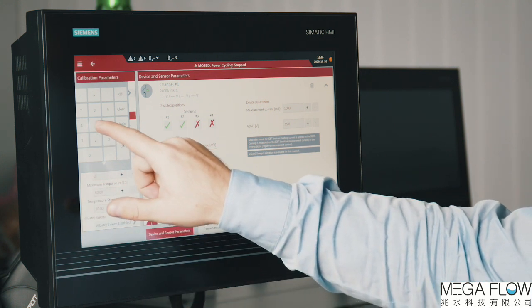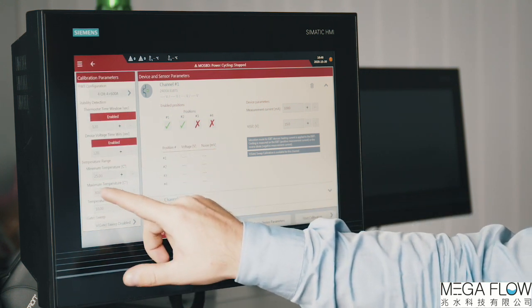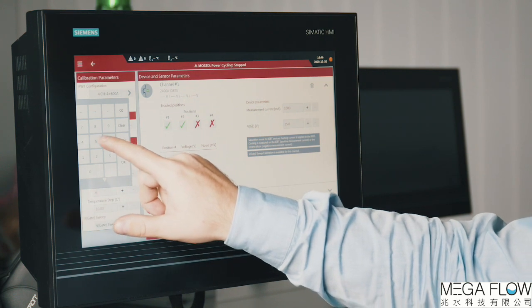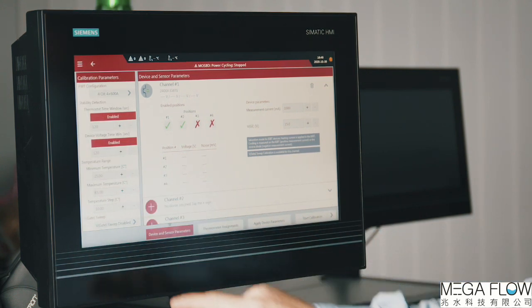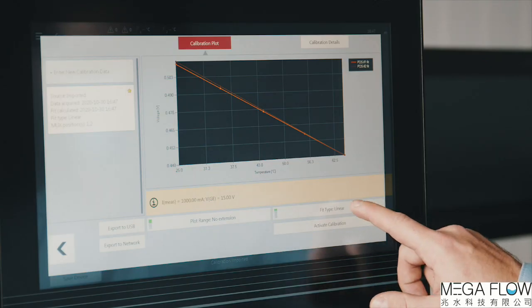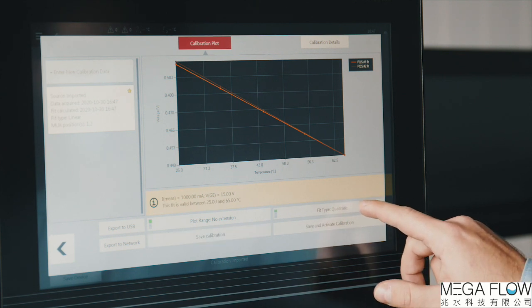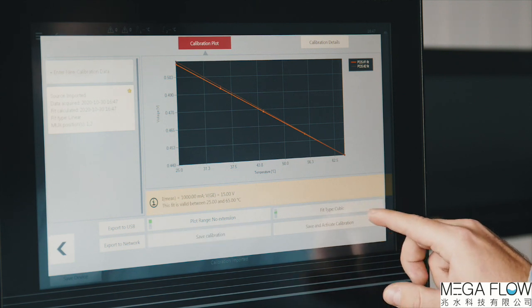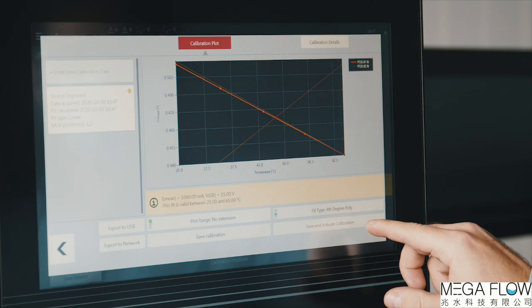During the temperature sensitivity calibration, the system automatically controls the chiller temperature and captures the device voltage as a function of temperature. At the end of the process, you can select what type of fitted curve to use for the transformation. Linear or higher order polynomial or exponential functions are available. Once we have the DUTs calibrated, it is ready to be used for thermal transient testing or power cycling.